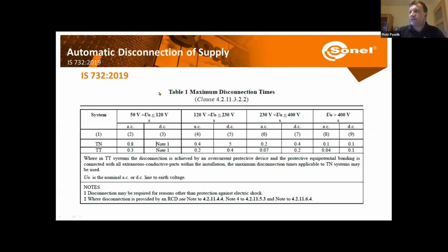So here, let's make it simpler. Let's just look at the table. And let's say typically we have a supply voltage of 230 volts AC. So in case of a TN system, the disconnection time is 0.4 seconds. And in case of a TT system, we have 0.2 seconds. Okay, so this is the time in which our MCB or RCD or some bigger circuit breaker should work.